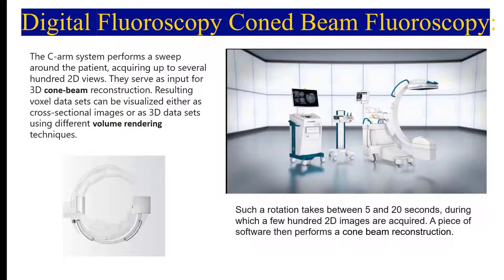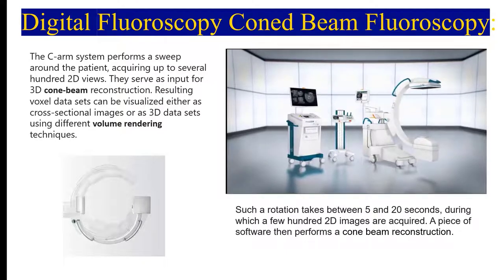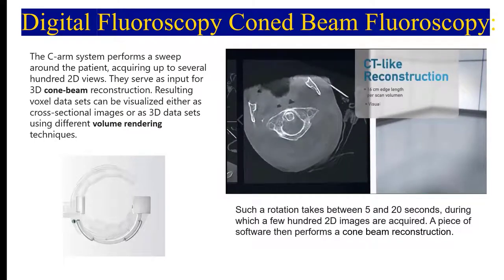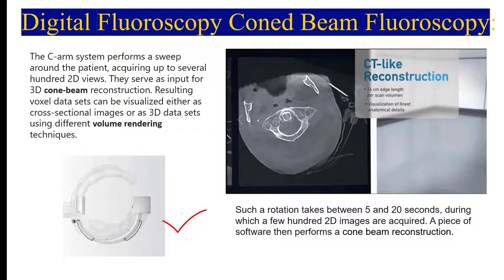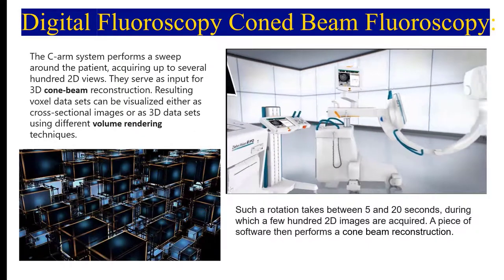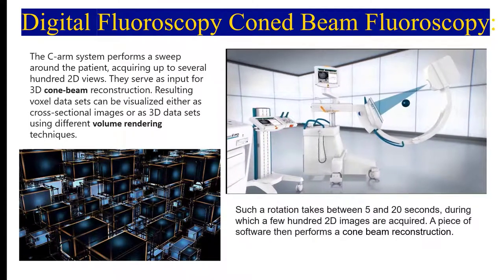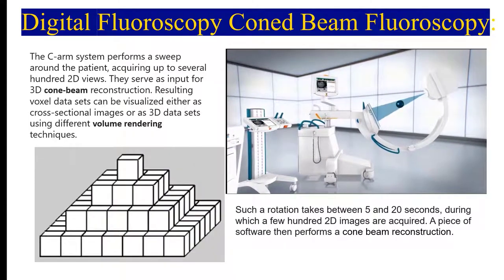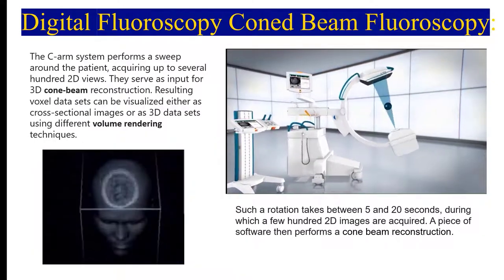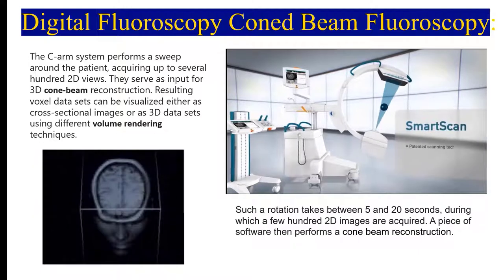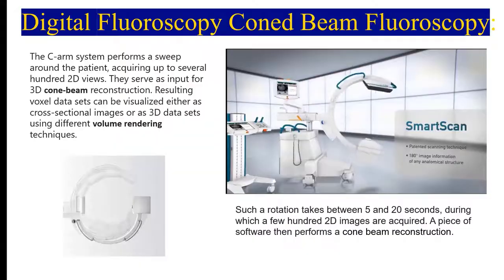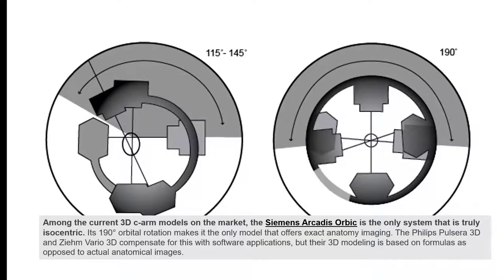Using cone beam CT in fluoroscopy, the C-arm performs a sweep around the patient acquiring up to several hundred two-dimensional views, which serve as input for the 3D cone beam reconstructions. This results in a voxel data set that can be visualized as cross-sectional images or as a 3D set of data through volume rendering. Such a rotation takes between 5 and 20 seconds.